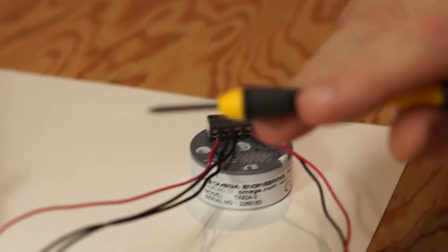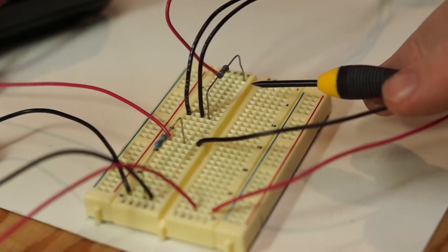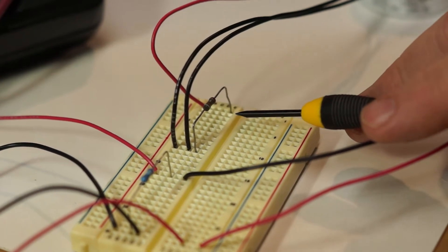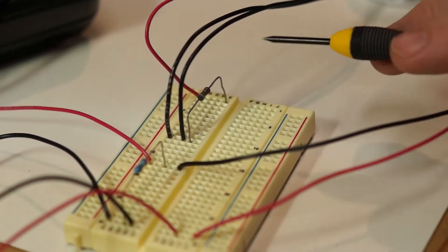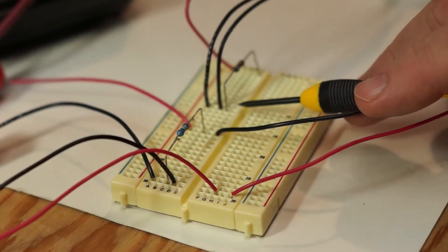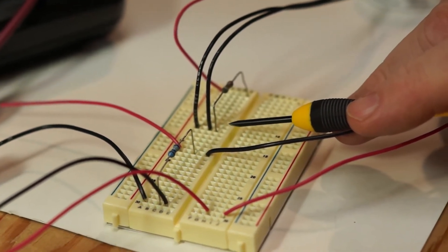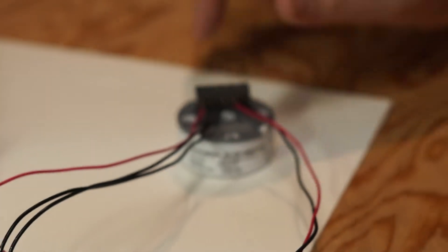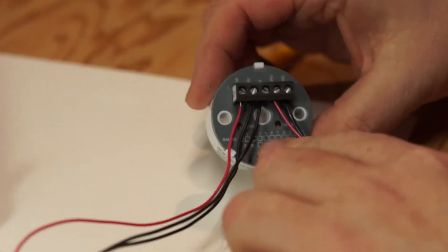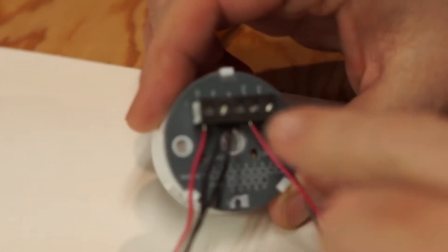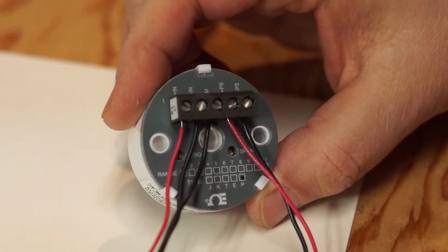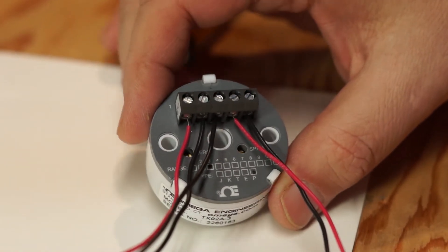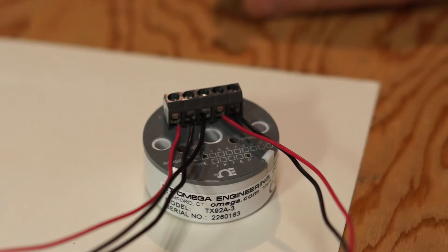Now over at the other end you'll see that there's a calibrating resistor here and this one's set up for the lowest resistance which is going to be 92.3 ohms representing zero degrees Fahrenheit. Now we've connected the two black wires because we're not using a real RTD, we're simulating it with a resistor. So this end and this end are connected back to this device. Now if I just flip this over a little bit you'll notice the letters on here indicate N minus, N plus and M. Those are the three connection points for the RTD. So make sure you've wired it up just the way I have it in this diagram and we'll start with the 92.3 ohm resistor.